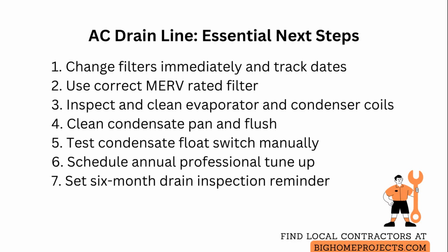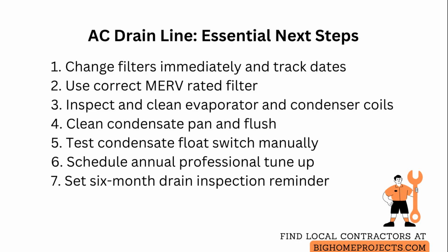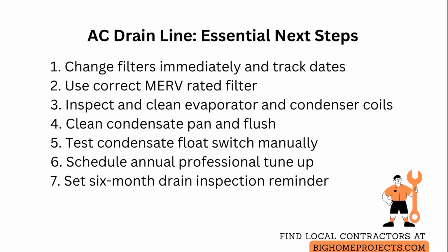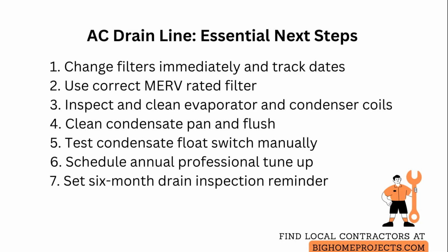Test the condensate float switch by lifting it manually to ensure the safety cutout engages, and that the switch connection is free of corrosion, because a failed float switch can allow overflow that damages ceilings and electrical components.